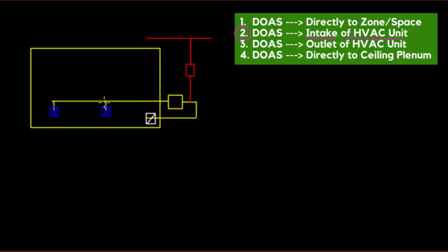For example, in the previous video we were talking about this office or conference room. I'm going to put in here conference room. So for the conference room, based on ASHRAE or the International Mechanical Code, ASHRAE 62.1, we established that my outside air requirement was 75 CFM.